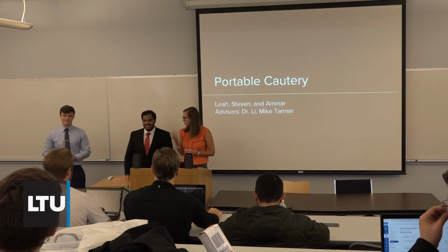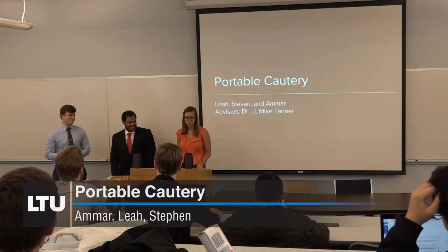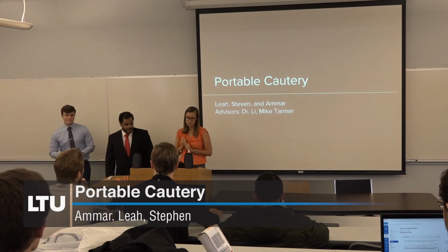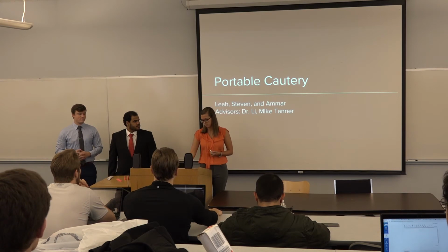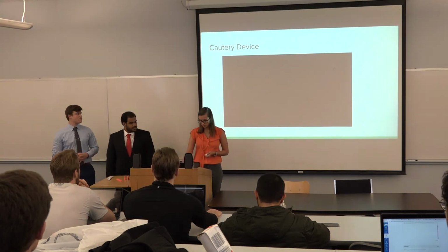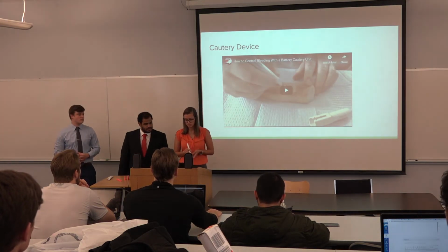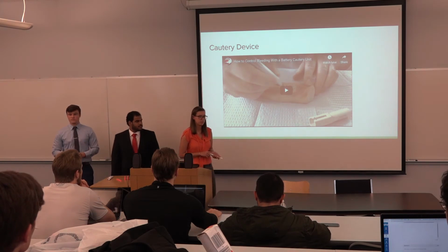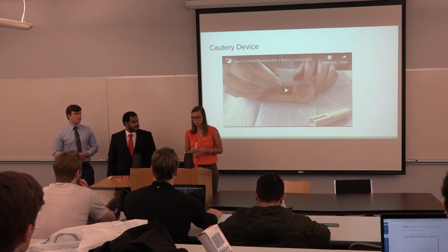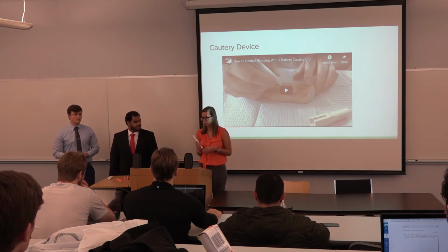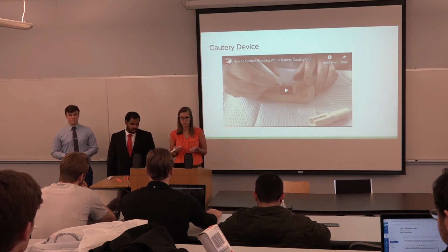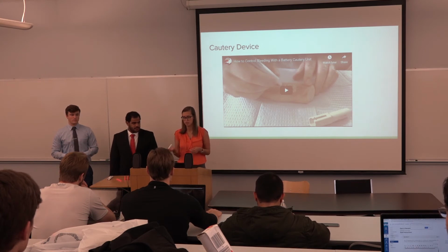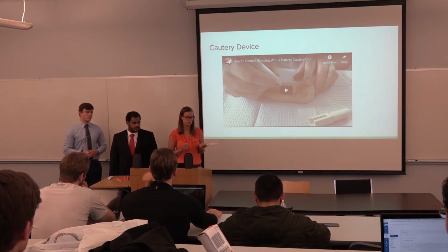So I'm Leah, this is Lenore, and Steve, and we're working on a portable cautery project with our industry sponsor, Mike Tanner, along with our faculty sponsor, Dr. Lee. Portable cautery devices are used in many different types of surgeries. There are two types: the portable ones like these, and stationary ones that some larger hospitals use, which get their current and electricity by plugging in to a large piece of machinery. We're focusing on these small battery-powered ones.